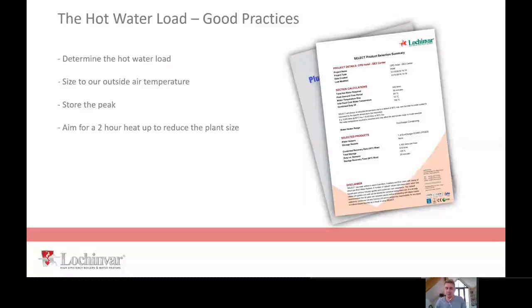And the reasons we do that are twofold. So you've got the volume in the system to be able to defrost. You've got a volume in the system to keep the compressors running so they work effectively. Insulation standards are now significantly higher than ever before. So every storage vessel, by default, is C rated as a minimum, so the insulation depths are upwards of 100 mil. So having these really well insulated vessels with low standing losses anyway gives us the ability to store more, downscale the size of the heat pump, reduce our initial capital investment, and get an overall system that runs more efficiently as a result, even though we've increased our standing losses with additional volume.